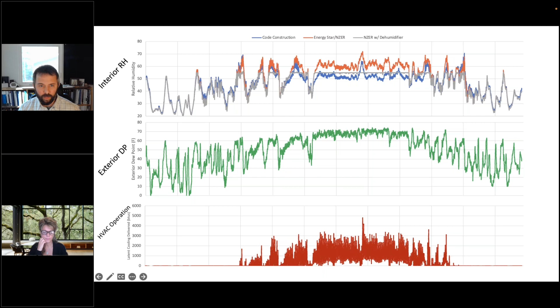Great point, Nikki. To illustrate that—in the shoulder season, say in Atlanta, we have times with mixed cycling of the cooling system. We only see a little bit of moisture removal, but we still have very high dew points and low dry bulbs during this time. So we see lower AC runtimes, which results in higher interior RH peaks, unless we have a way to remove the moisture—a dehumidifier is able to remove moisture during this time, even though the AC is not running.